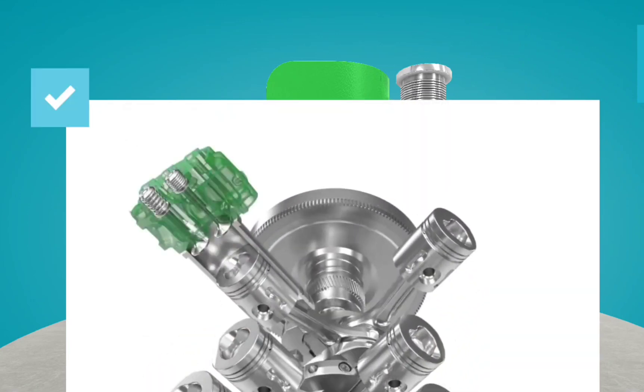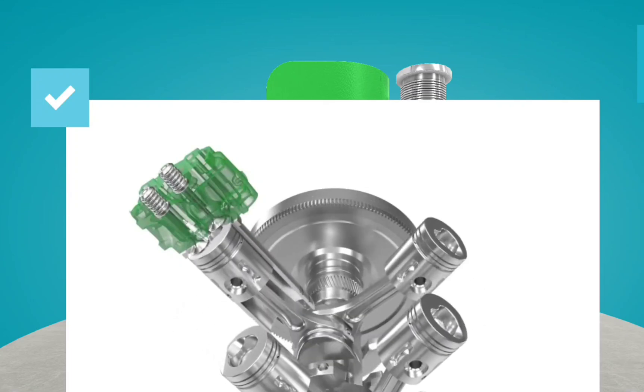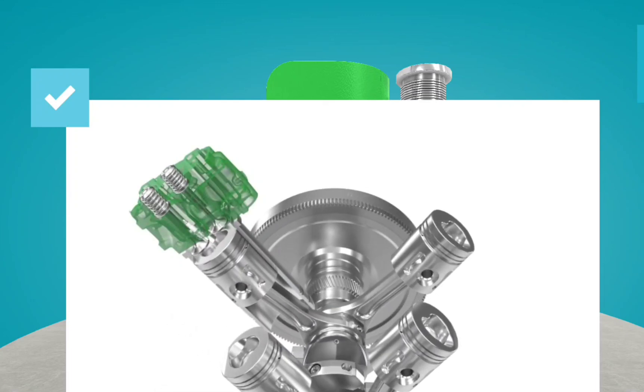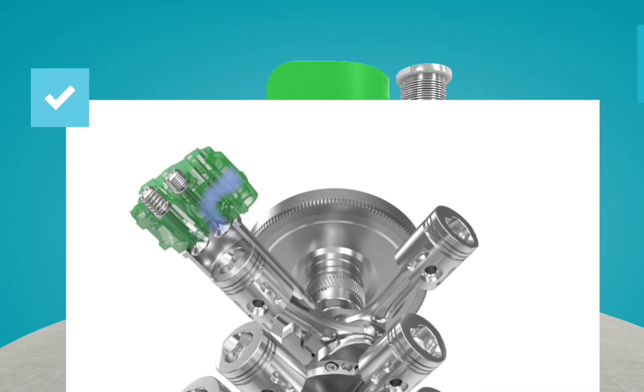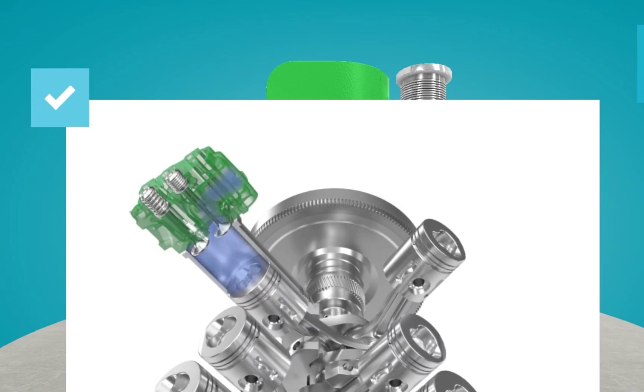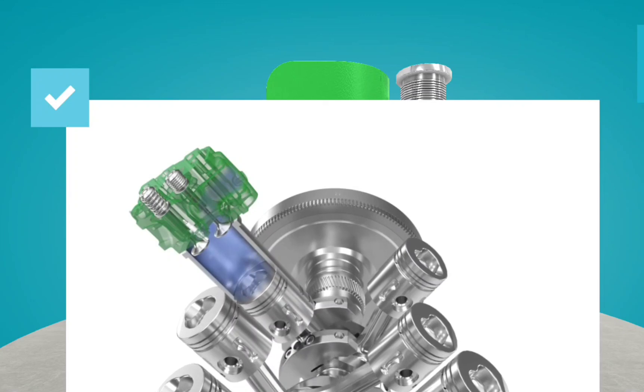Jenbacher gas engines are spark-ignited four-stroke engines. Let's look at each stroke in detail. During the intake stroke, the inlet valve is opened, and the piston moves downwards, sucking the air-gas mixture into the combustion chamber.